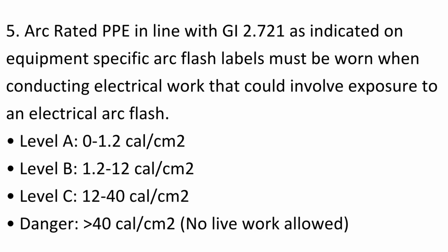5. Arc-rated PPE in line with GI 2.721, as indicated on equipment-specific arc flash labels, must be worn when conducting electrical work that could involve exposure to an electrical arc flash. Level A, 0 to 1.2 cal/cm². Level B, 1.2 to 12 cal/cm². Level C, 12 to 40 cal/cm². Danger, greater than 40 calories per square centimeter, no live work allowed.